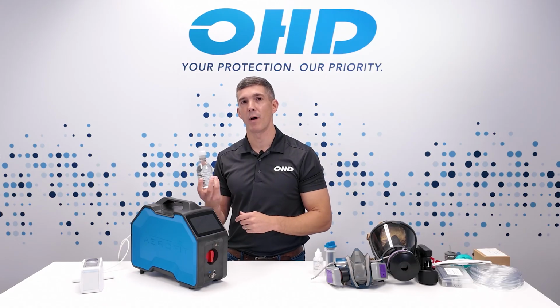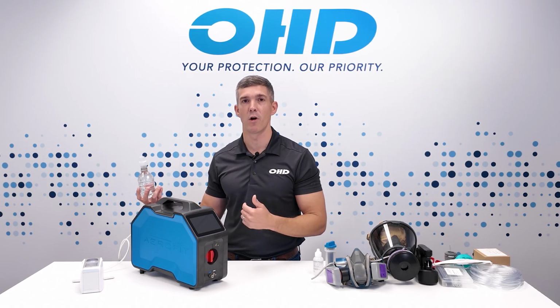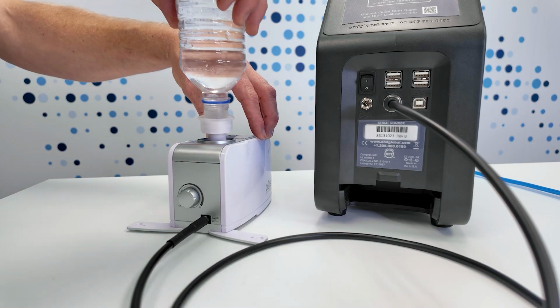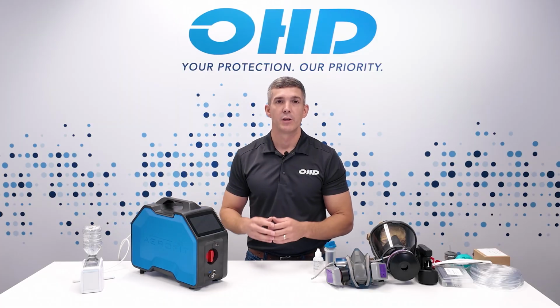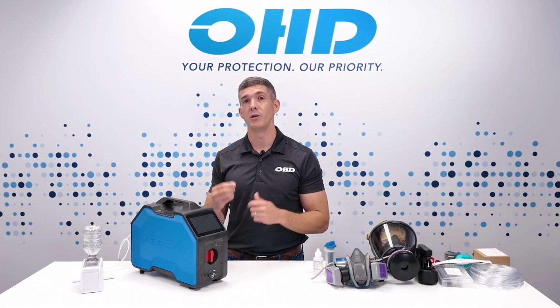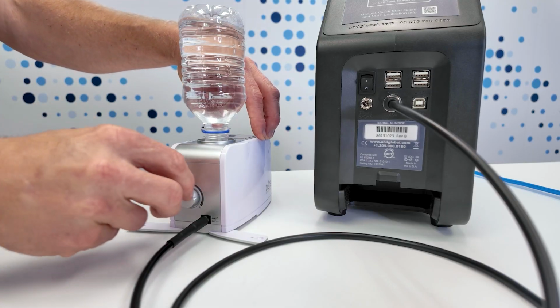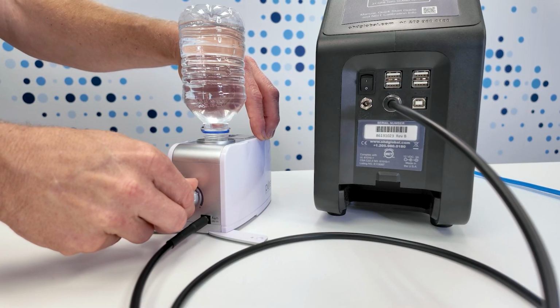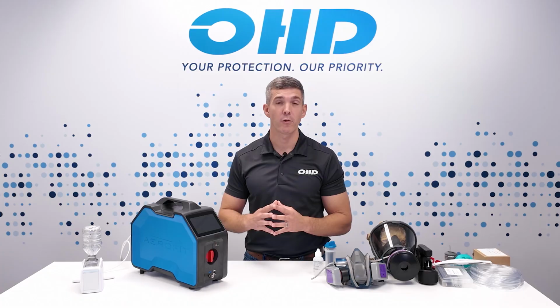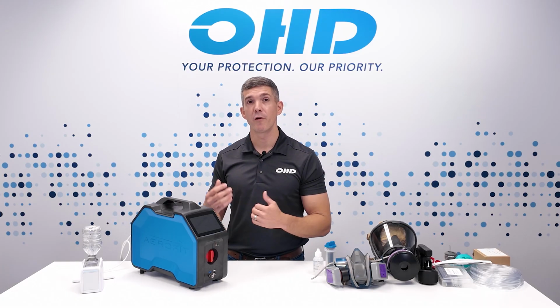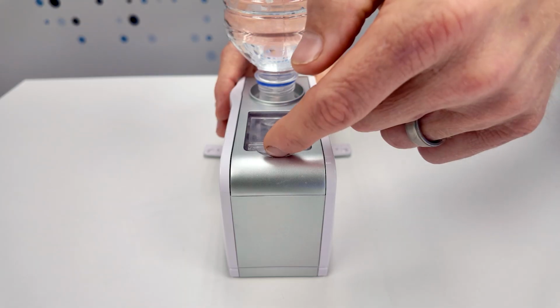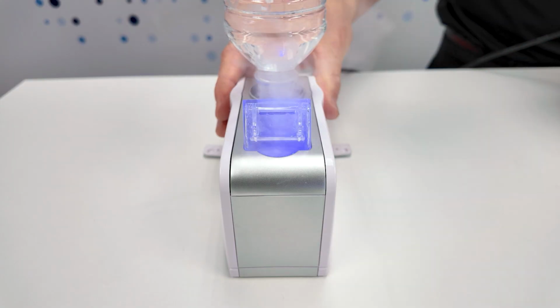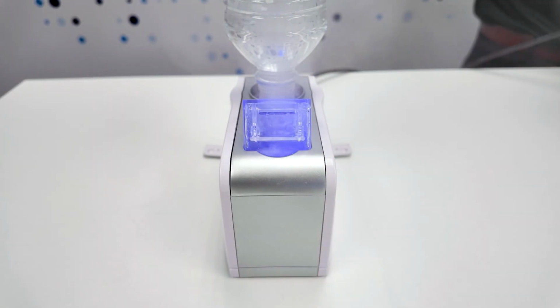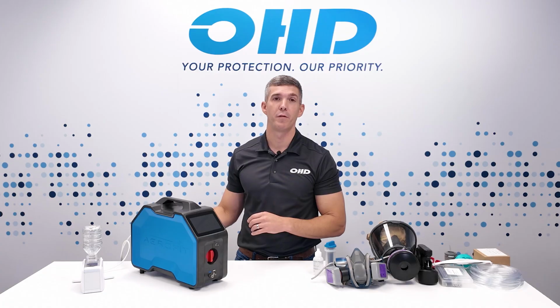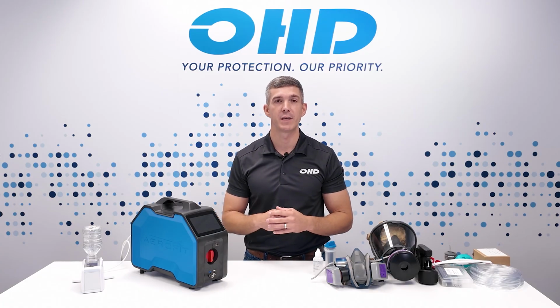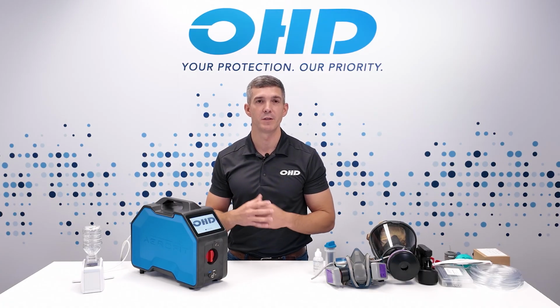Next, place the connected bottle upside down in the reservoir to allow the particle generator to fill. Turn the particle generator's knob to your desired output. Full is recommended. To finish the particle generator's setup, open the front window to ensure it allows maximum generation. Next, flip the switch on the back of the AeroFit to turn it on and wait a few seconds while it completes its startup cycle.